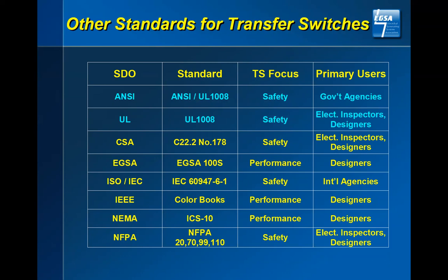If you're doing an actual installation under that 99 or 110 application, healthcare or emergency systems, when you put that standby generator into operation, it is specifically stated how you need to test it. Usually that is a 4 to 8 hour load bank test before you can then commission that generator in order to be used as your backup power.